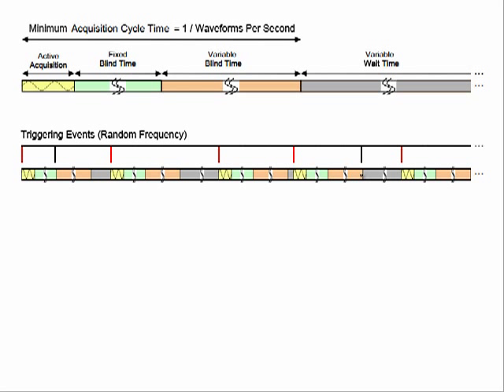And then down here again, before it finishes the blind time, it has a trigger which is ignored. So with just random triggers coming in, you see that the acquisition cycle time is varying in length, and so then also are the waveforms per second.